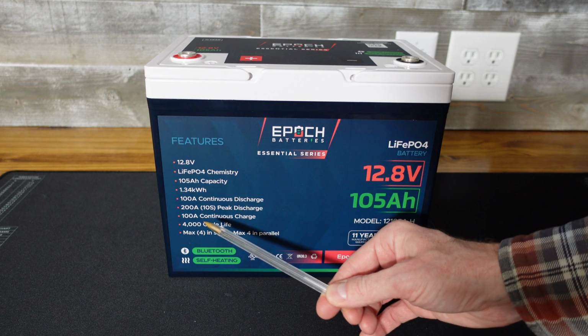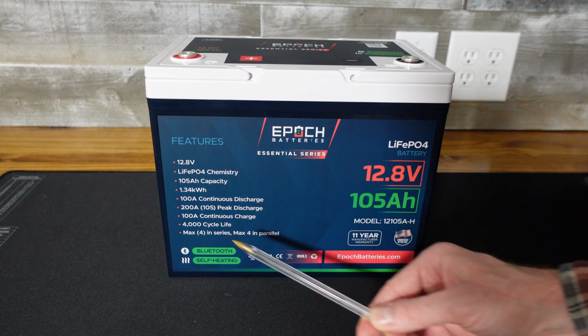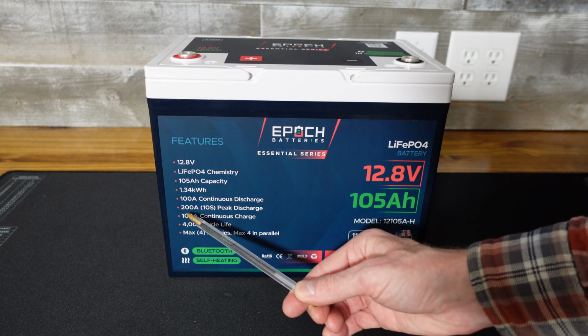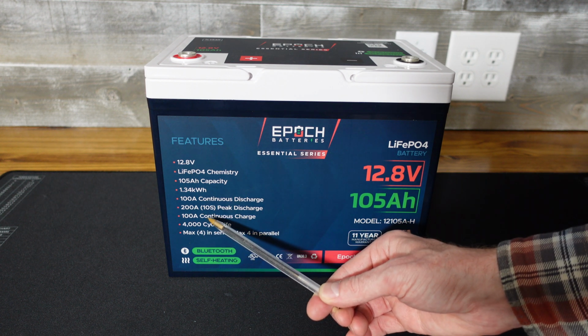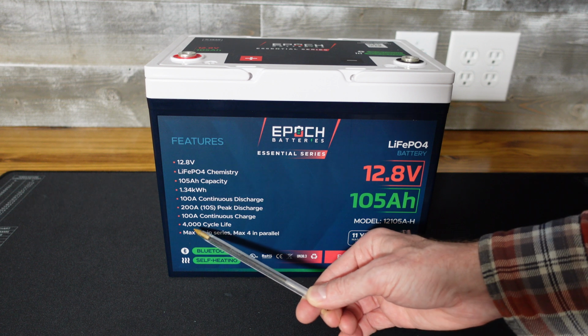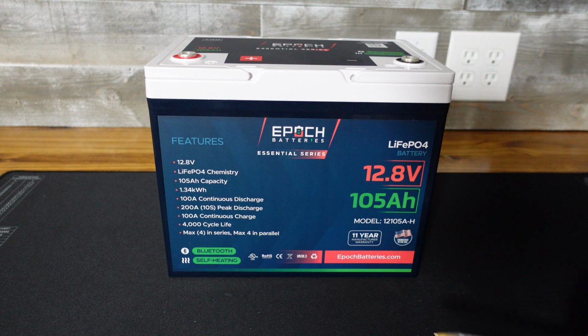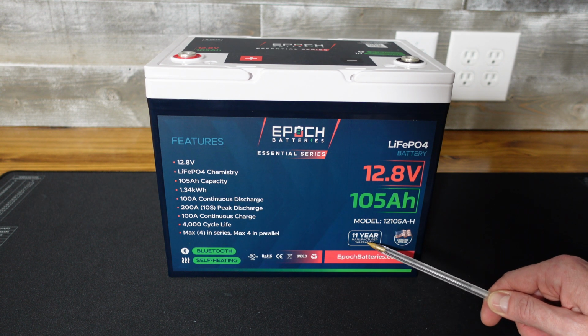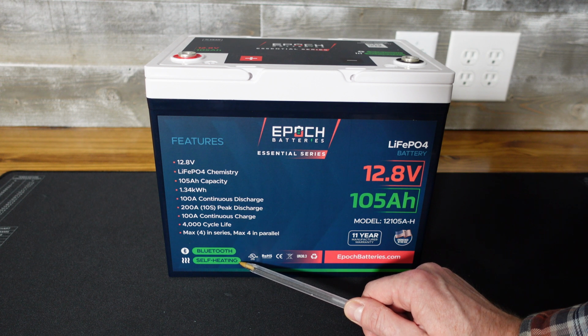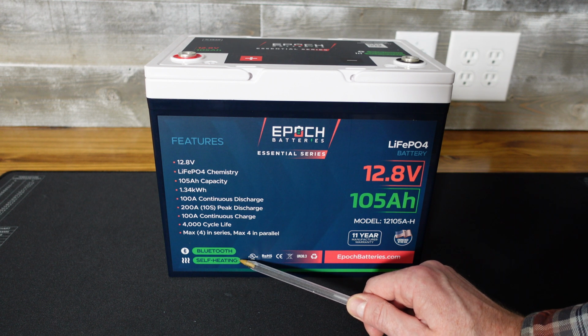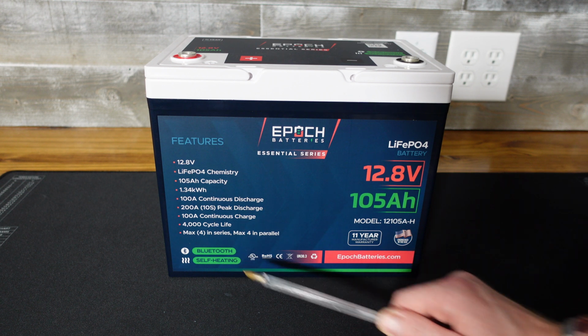It has a maximum discharge rating of 100 amps continuous, and a maximum peak discharge rating of 200 amps for up to 10 seconds. It can be charged up to 100 amps at a constant current, and it does come with a very lengthy 11-year warranty. This battery is also self-heated, so it can be charged when the ambient temperature is below freezing, and it includes Bluetooth support.